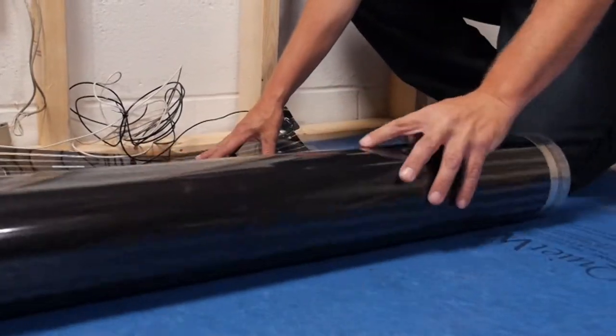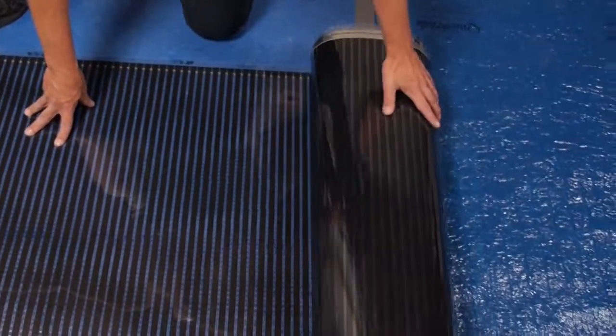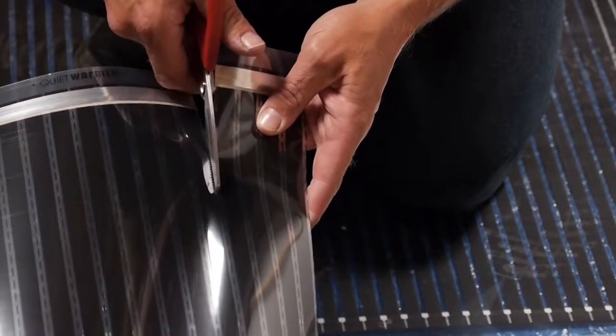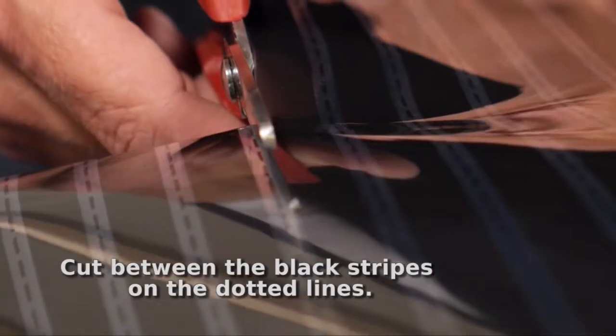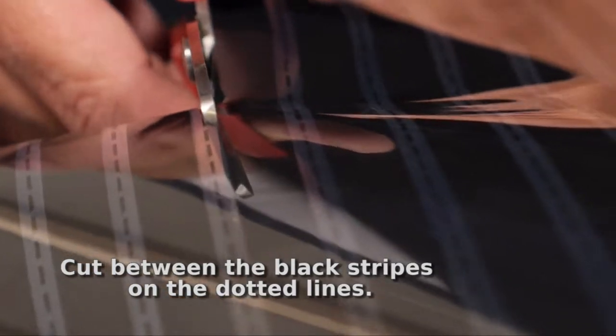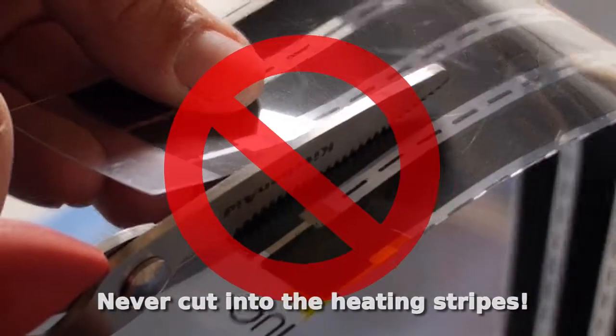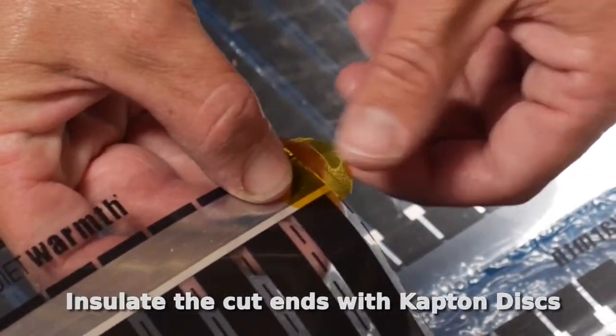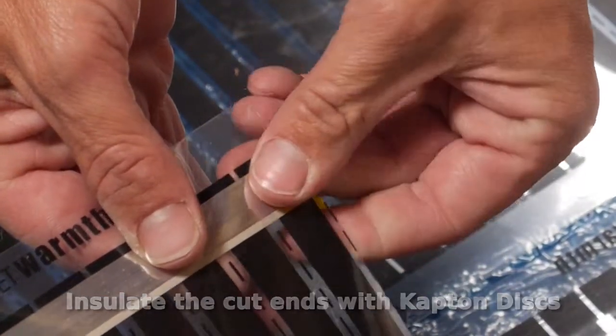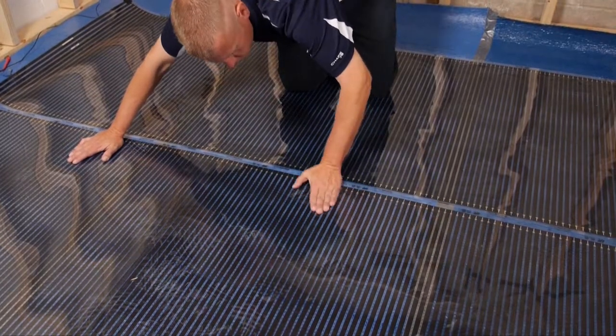Using the diagram you made earlier, unroll the heating mats in the desired areas of the room. You may cut the mat to shorten the length in order to fit the layout of your plan. When customizing the heating mats, cut through the clear area in between the heating stripes on the dotted lines, and never cut into the actual heating stripes themselves. Insulate the cut ends of the metallic bus bar strips with the Kapton discs provided with each roll. Once the heating mat is rolled out, it should be free of any kinks, ripples, or creases.